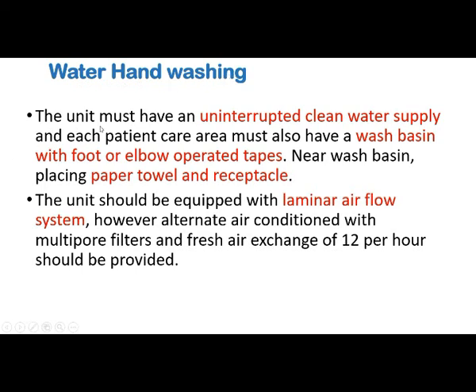Next, hand washing. The unit must have an uninterrupted clean water supply, and each patient care area must also have a wash basin with a tap operated by foot or elbow. Near the wash basin there must be paper towels and receptacles, that is waste bins. The unit should be equipped with a laminar air flow system, with inflow and outflow. However, alternatively air conditioning with multi-pore filters and a fresh air exchange of 12 per hour should be provided. That is about the air flow and the hand washing system.